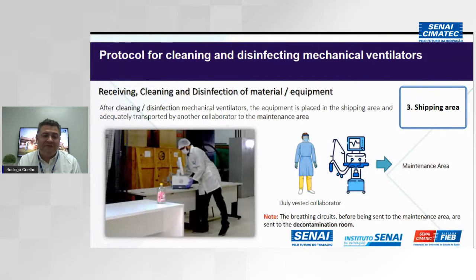After I do the whole cleaning procedure, I need to transport this equipment with all its pieces to a shipping area. You can see another employee picking up this equipment to bring it to what we call the traceability area, where I check the whole operation system of this machine, check the alarms, check the cycling when I put it on power, and determine what kind of maintenance is necessary.